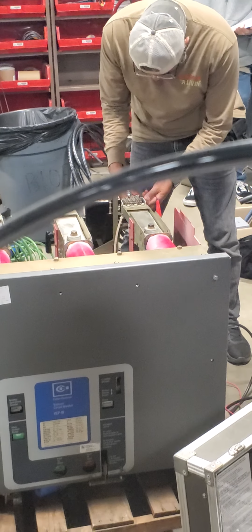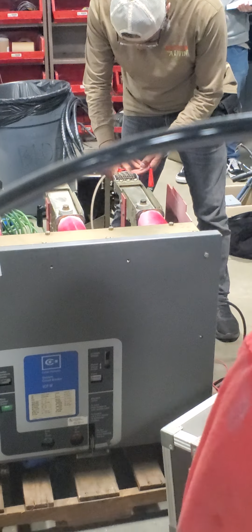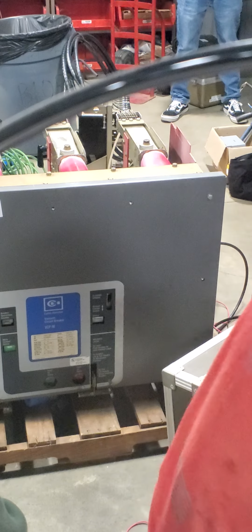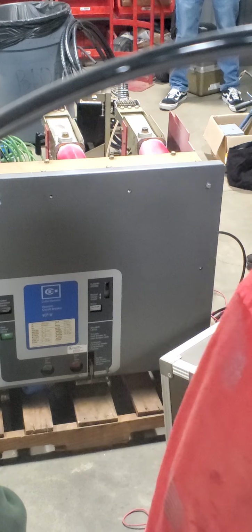Santiago had the question: is the HIPOT going to be on the final exam? It won't be, because this is the only breaker here that would even qualify for a HIPOT test. As we looked at the MTS, that line said integrity test or dielectric withstand test on a breaker would only be for your very large breakers. You're not going to push tens of thousands of volts through those little guys, unless you want a new breaker. But in an even field, you can expect bigger DLRO, basic inspection, those kinds of things.